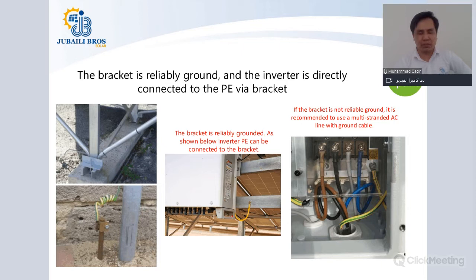So in order to discuss the picture, to give you a background, our Huawei inverter has earthing points inside and outside of the inverter. These both earthing points are at the same potential. So if you are earthing inside the inverter, you will not be needing earthing on the outside. And if you are using the earthing point outside the inverter, then you do not need to do the earthing inside the inverter. We have many different inverter models. The smaller ones have only one earthing point at the outside, but the bigger ones come with the removable cabinet where you can do some connections. So those inverters come with 2 points of earthing, and you can use any of them.